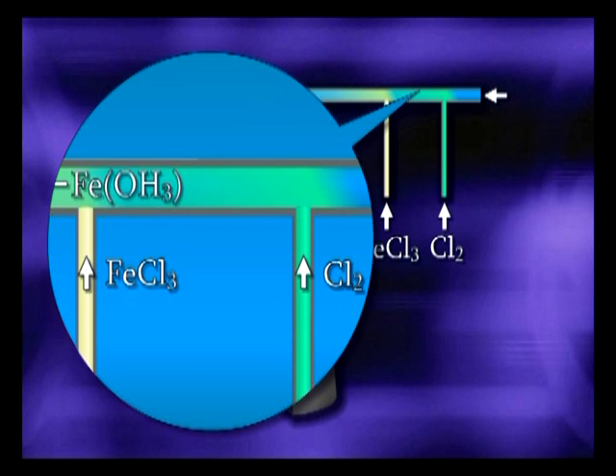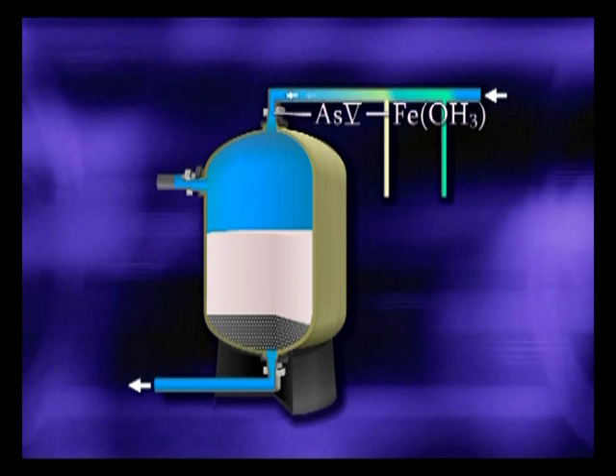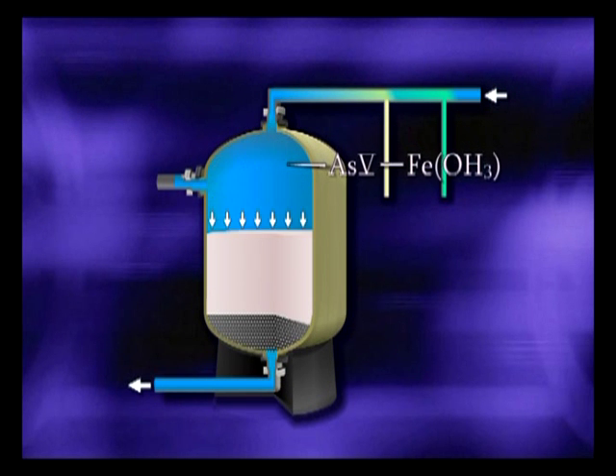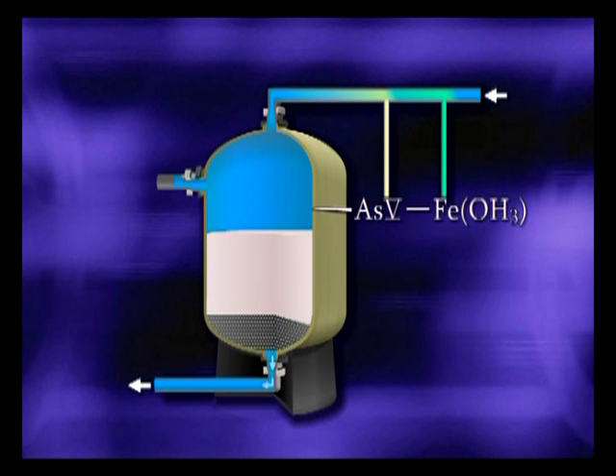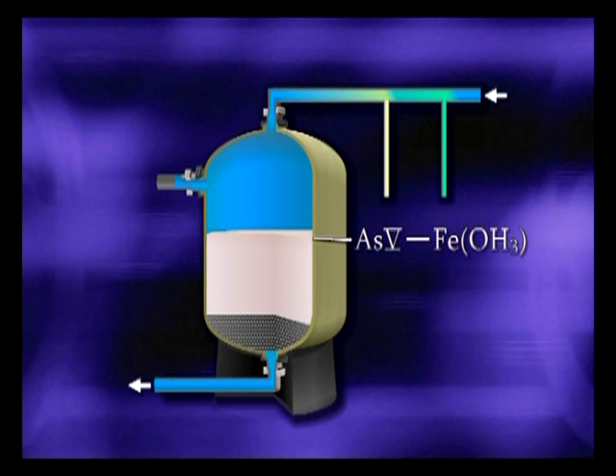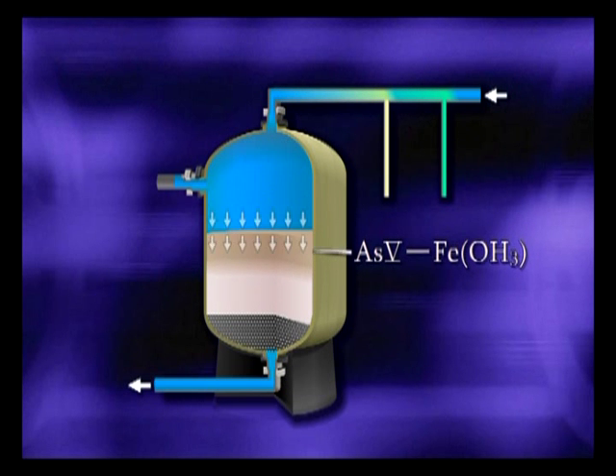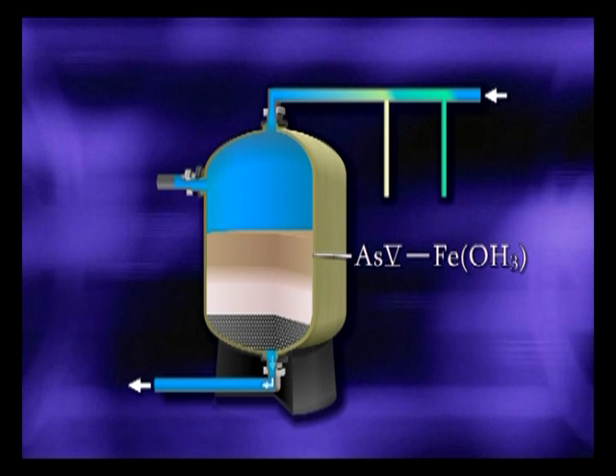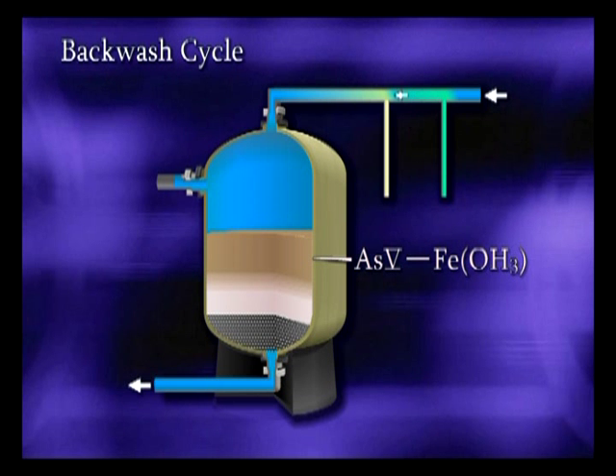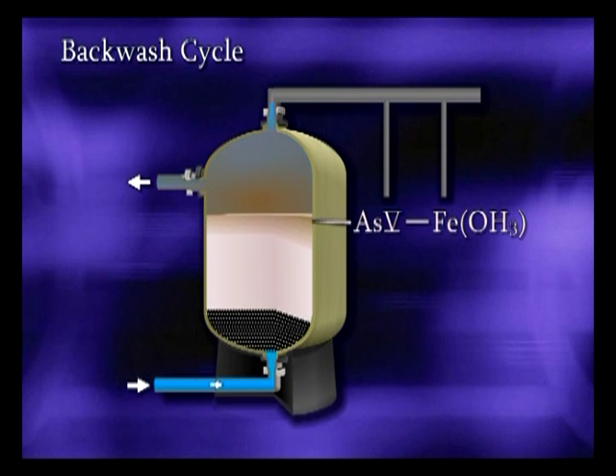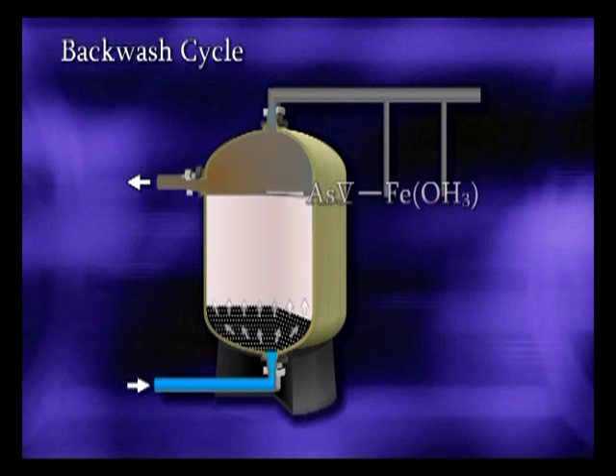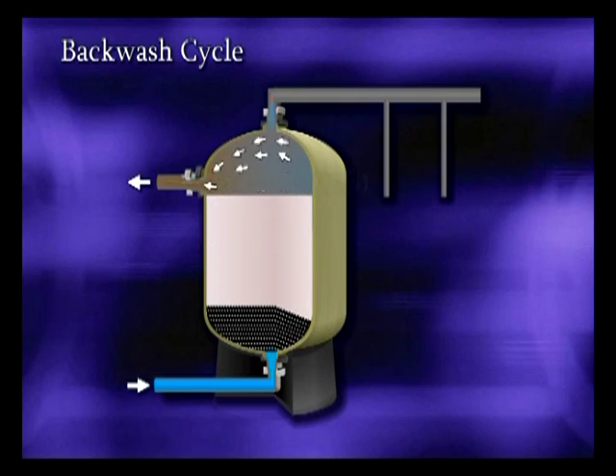The hydroxides and arsenic-laden water are held in a retention tank to allow the co-precipitation and adsorption process to occur. The arsenic and iron precipitates are then filtered from the water — in this example by a pressure filter vessel. The filters load with precipitates until partially loaded, then are backwashed. The backwash waste is directed to either a sanitary sewer or dedicated waste system.